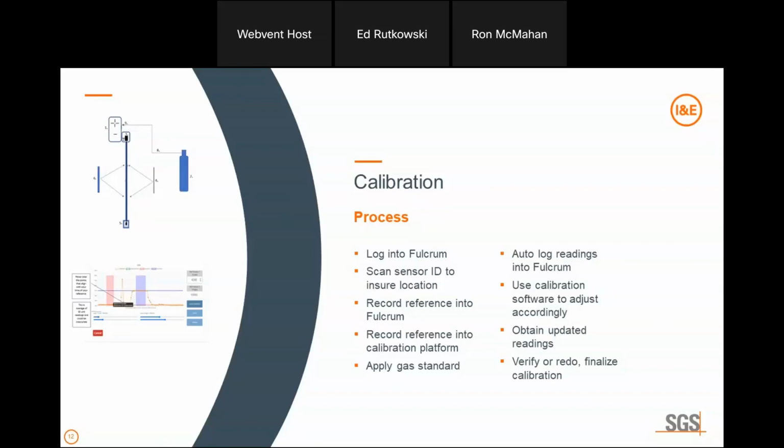So we determined very early that we had some people that would use the instruments and they would be too close to the CO2 sensor or whatever, and it would cause this variation. And so those kinds of things come into play. And so number one, are your reference instruments working properly? Are they calibrated? Number two, use them effectively so that you don't cause an interference or any inaccuracy when you're recording these, when you start to do the comparison and do the calibration.